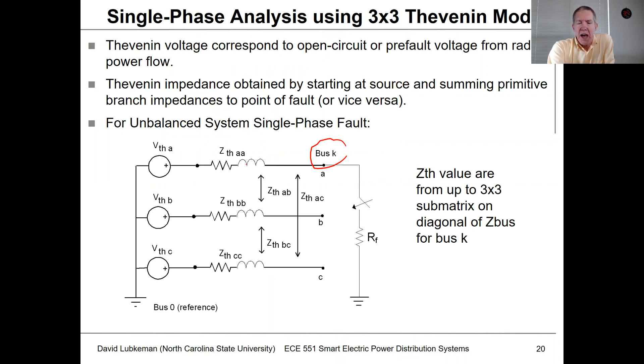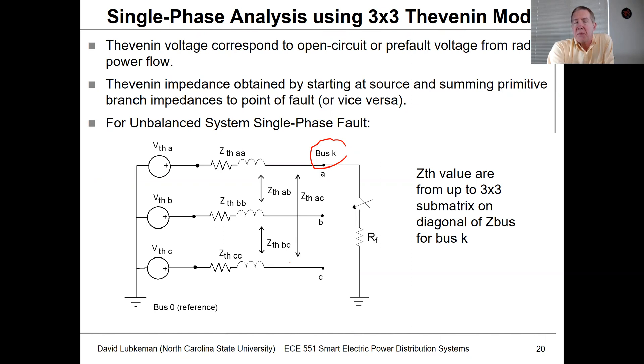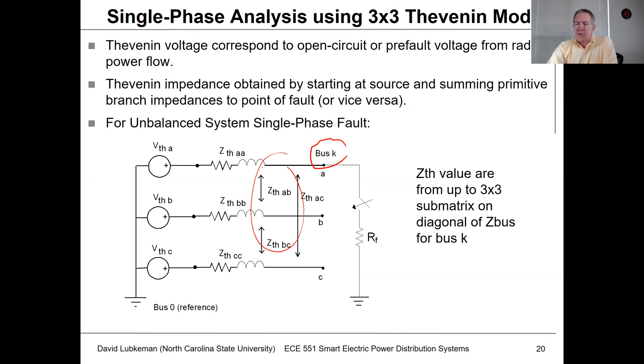What we're going to have is the three-by-three impedance values: Z_AA, Z_BB, Z_CC, and then the off-diagonal terms Z_AB, Z_AC, and Z_BC. These values give us coupling between the phases. You can get this a number of different ways — through inspection, or if you have the bus impedance matrix, you can pull it out of there as well.